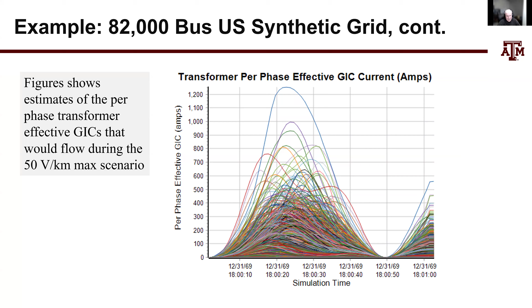Now, compared to a GMD, I will say this is a much shorter duration event. It's over within, in this case, about 60 seconds. So what could occur during a HEMP? There might be little or no warning, in contrast to a GMD, where we could observe solar activity at least a day ahead of time. With a HEMP, we might not have any warning. Because this requires an adversary, that adversary would have some choice on the time, location, and number of events that might occur. So when the grid is subject to this event might not be arbitrary.